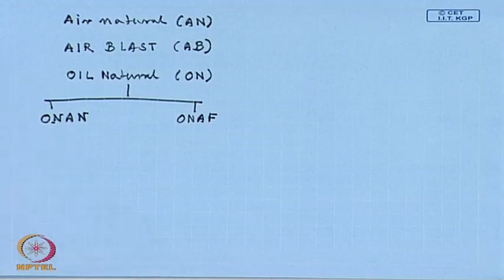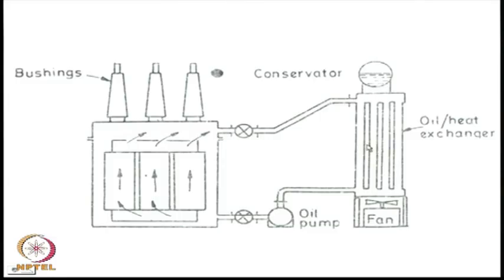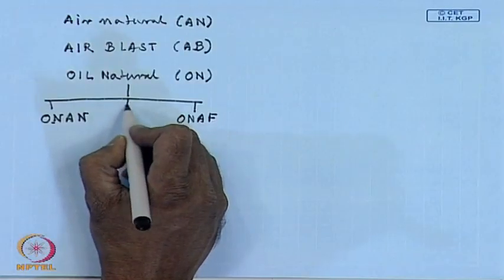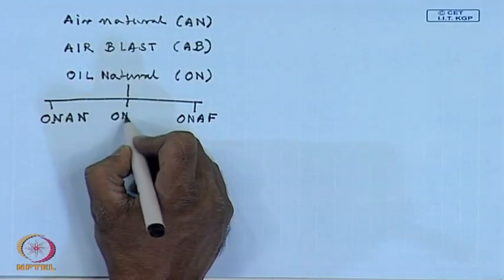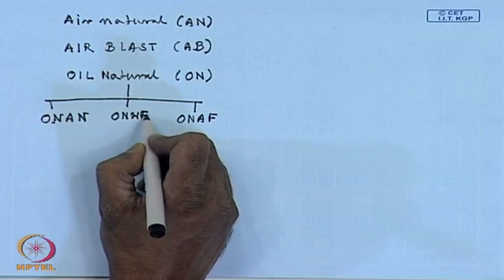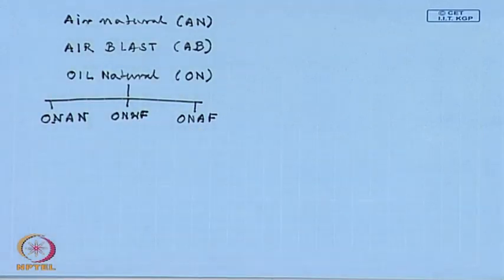This heat exchanger can also be cooled by forcing water to circulate around the oil carrying pipes, then it will be called oil natural water forced. This is used normally in hydroelectric generating stations for the generator transformer, because a large quantity of water at a sufficient head is available, and water is a better medium of cooling than air.